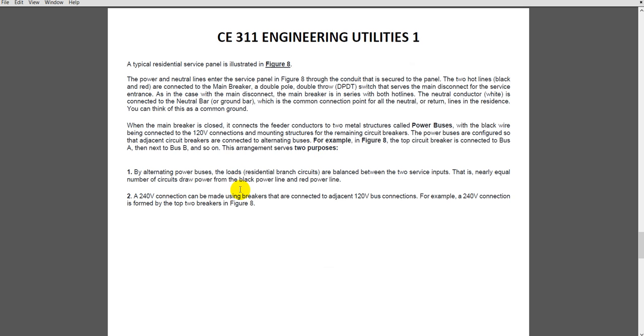By alternating power buses, the loads are balanced between two service inputs, nearly equal in the number of circuits drawing power from the black line and red power line. A 240 volt connection can be made using breakers connected adjacent to a 120 volt bus connection. For example, 240 volts is formed by the top two breakers in the figure.